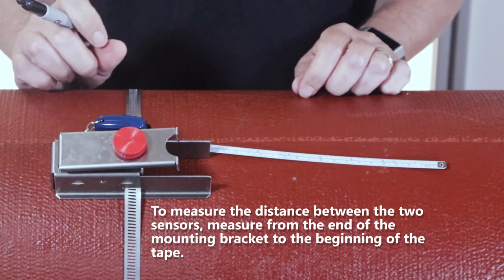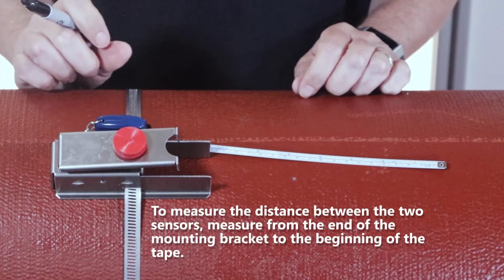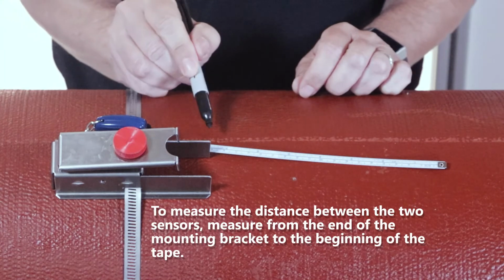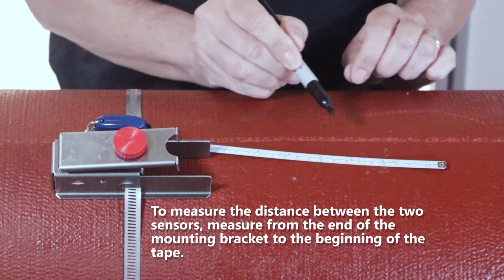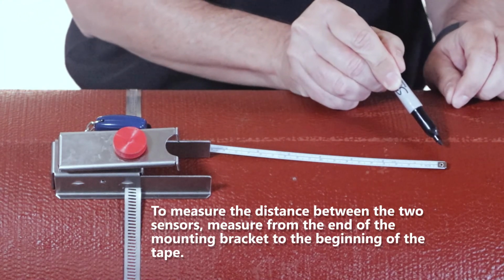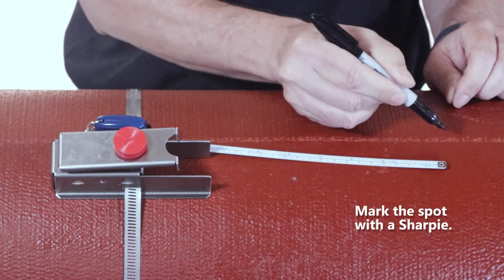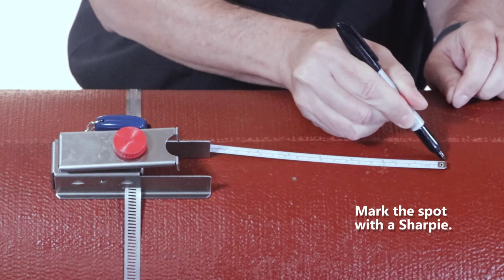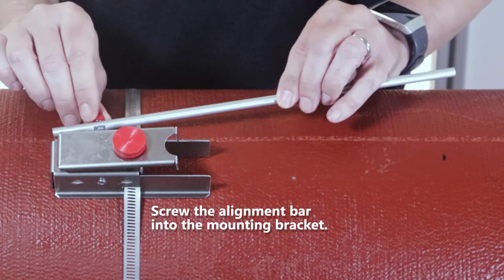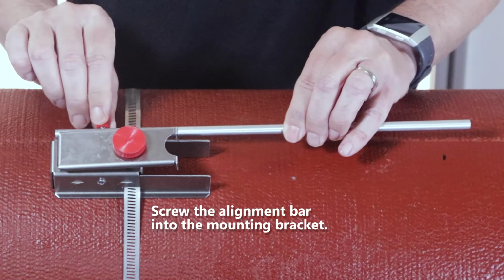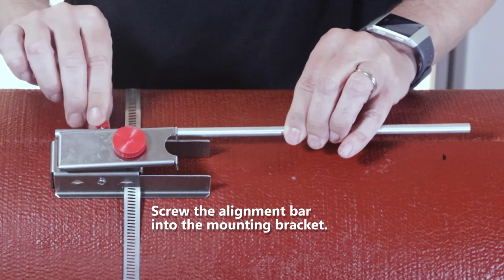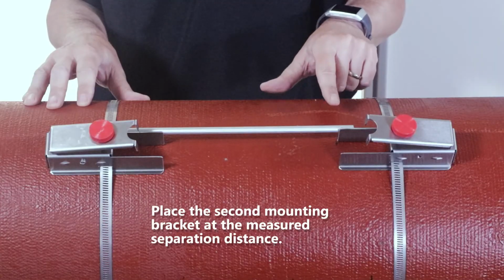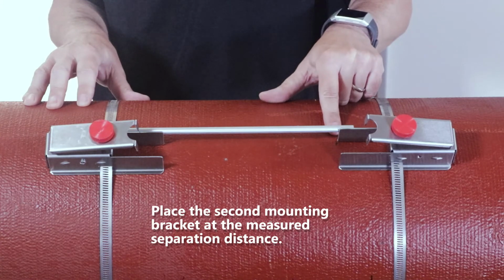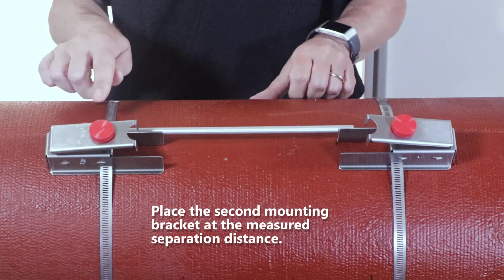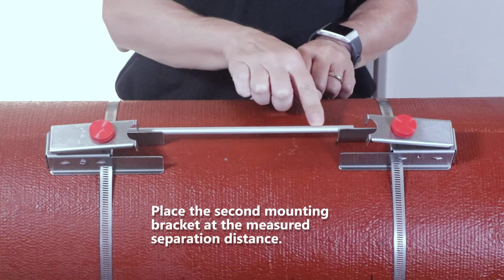Now it's time to measure the distance between the two sensors. We do this by measuring from the end of the mounting bracket to the beginning of the tape. In our example, 7.7 inches or nearly 7 3/4 inches. Then we mark the spot with the Sharpie. It's time now to install the alignment bar. We simply screw the alignment bar into the mounting bracket. We've placed the second mounting bracket at the measured separation distance. The alignment bar assures that the brackets are parallel.